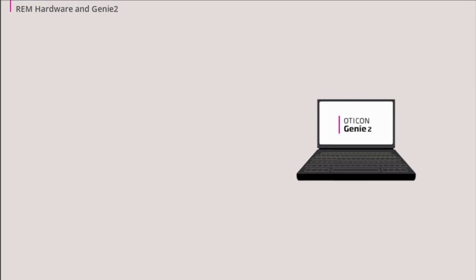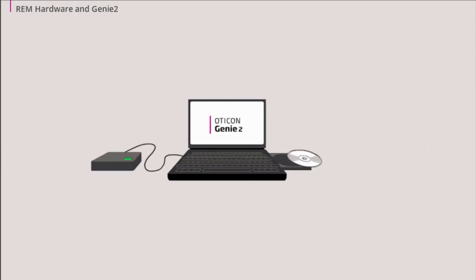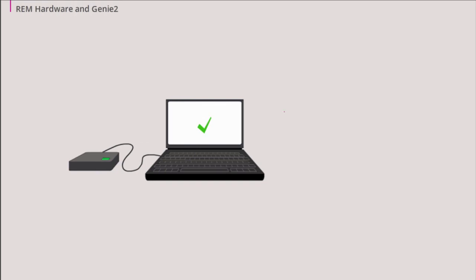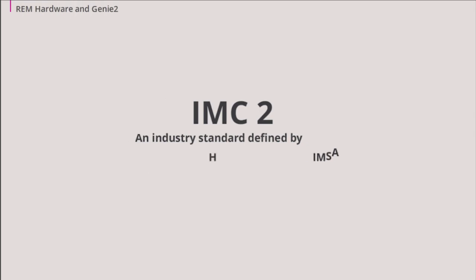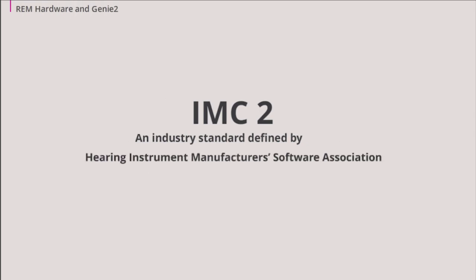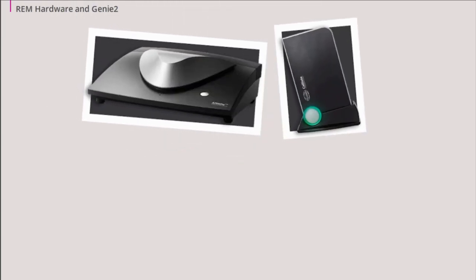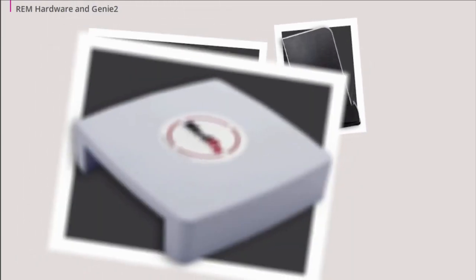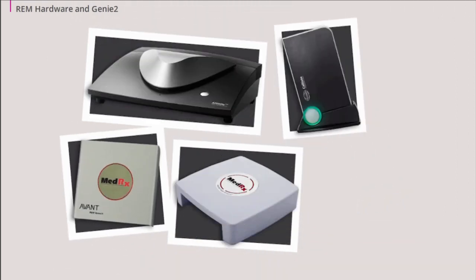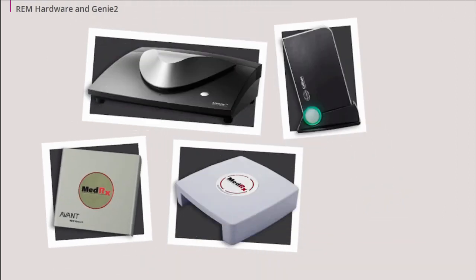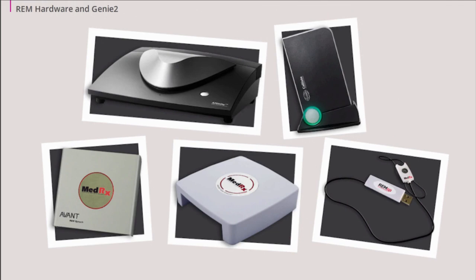To perform REM AutoFit in Genie 2, your REM equipment and REM software must be installed on the same PC as Genie 2. Genie can communicate with equipment that supports the IMC2 protocol through NOAH 4.4 or later. IMC2 is an industry standard for REM equipment defined by HIMSA, the Hearing Instrument Manufacturers Software Association. If you use Genie 2 stand-alone, you can use Affinity and Callisto equipment from InterAcoustics and AVANT REM Speech Plus, AVANT REM Speech and AVANT REM SP from MedRx.